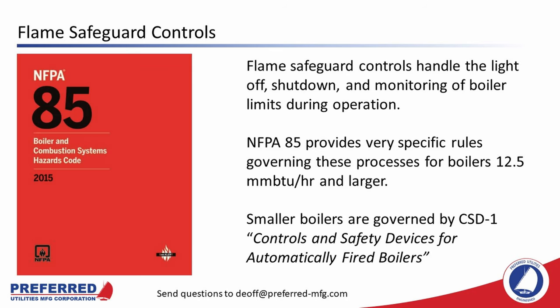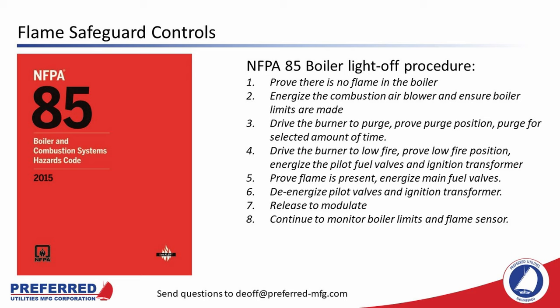The first part of boiler control we're going to cover is flame safeguard controls. The flame safeguard system lights off, shuts down, and monitors the boiler for safe operation while it is running. It monitors boiler limits such as high steam pressure switches, low water cutouts, fuel pressure switches, and flame scanner inputs to ensure the boiler is running safely. Flame safeguard controls are covered by NFPA 85.